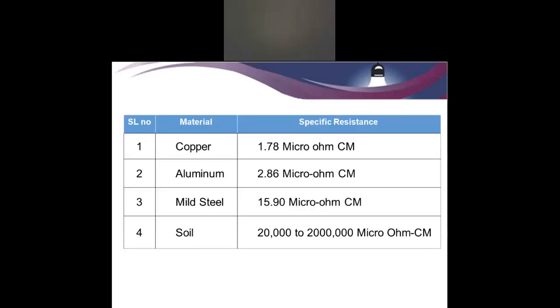So we see copper has very low resistance in micro-ohm centimeters, so it is used most of the time. But low resistance alone is not the criteria to create zero earth resistance, as you see soil is not at all a good conductor.